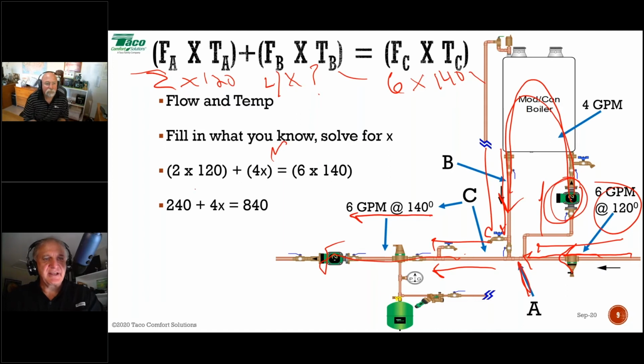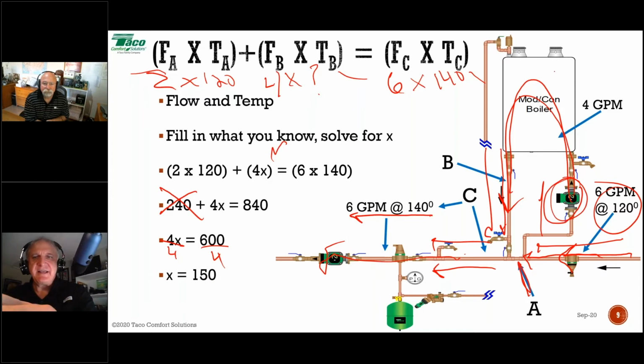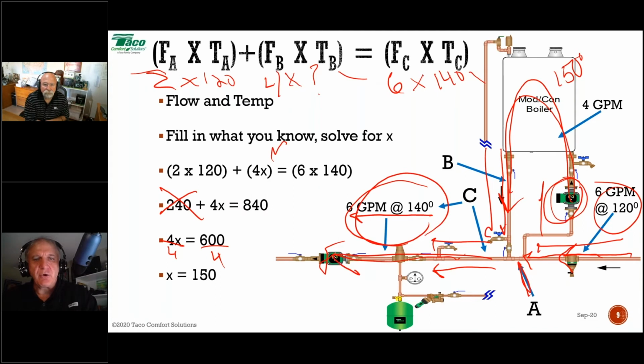To solve for X, the first thing I got to do is isolate X. So the first thing I got to do is get rid of the 240 over here. With one of these formulas, what you do to one side, you got to do to the other. So I'm going to subtract 240 from each side. That's going to give me 4X equals 600. To solve for X, I divide both sides by 4. So 4X divided by 4 is X. 600 divided by 4 is 150. So in this example, I'm going to need that boiler to make 150-degree water in order to have the required 140-degree water in my system.